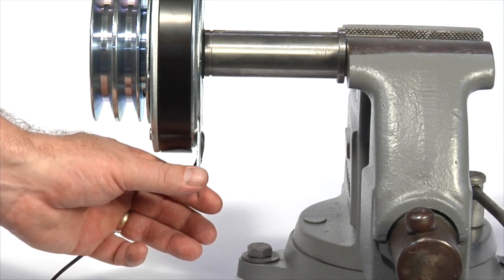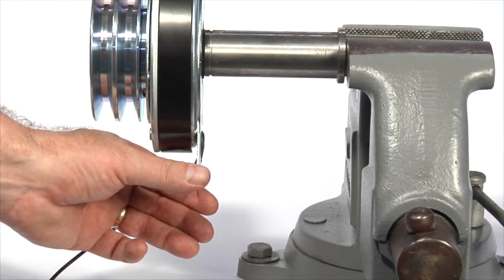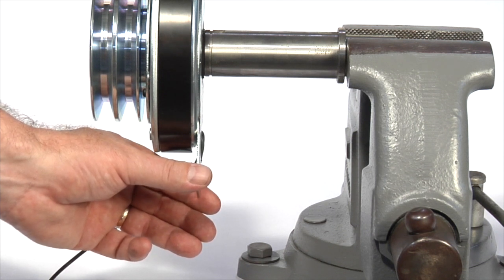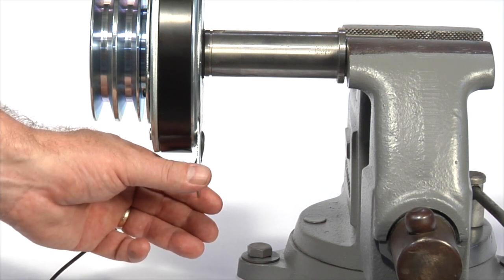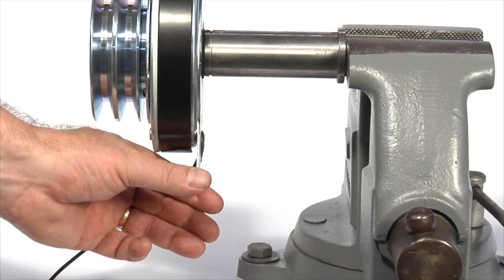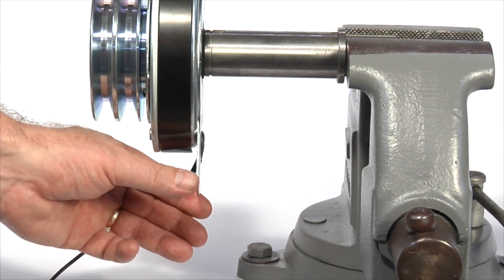The torque tab on the back of the clutch needs to be loosely restrained. It is very important to have approximately an eighth of an inch of axial and radial movement to prevent field bearing damage.